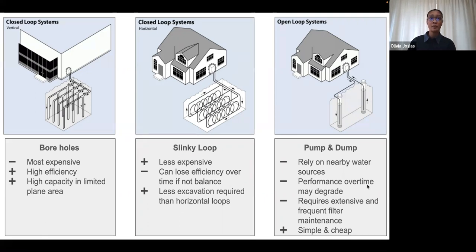There's also the possibility for slinky loops to lose efficiency over time from lack of balance. Due to this system being closer to the ground level, it is more susceptible to outside temperatures than a deeper in-ground system would be. Then there's the open loop system on the right. That works by extracting groundwater and dumping it back into the ground. However, we don't know about the groundwater resource situation, so it makes more sense not to overcomplicate things for our geological space.